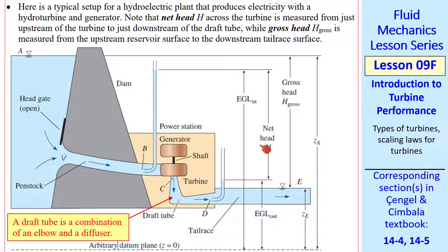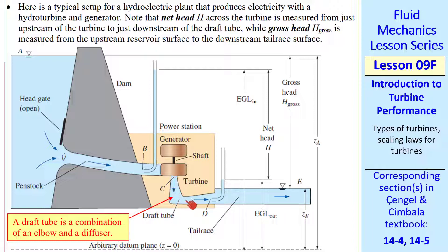Here's a typical setup for a hydroelectric plant. For a dam, there's a gross head, defined as the elevation difference between the water surface upstream and downstream. There's a large pipe called a penstock with major and minor losses, so the head actually available to the turbine is lower — we call this the net head. If you put a total pressure probe as shown, the height gives the EGL in and EGL out. The draft tube expands out significantly so the area at exit is much larger than at entry. The draft tube is a combination of an elbow and a diffuser.